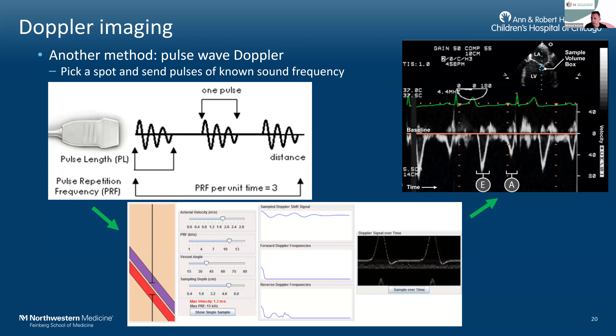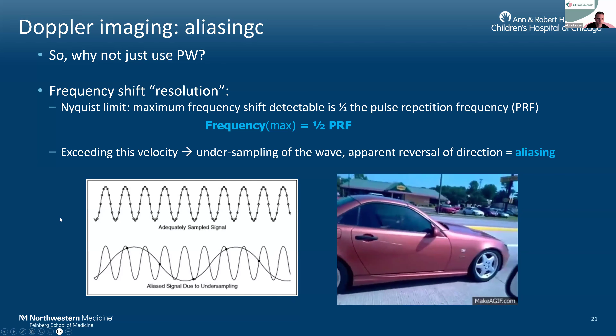The limitation of PW is that physics caps the maximum velocity that can be detected. In a famous equation by the physicist and engineer Harry Nyquist, the maximum frequency shift detectable, or Nyquist limit, is found to be half the pulse repetition frequency. Any velocity that shifts the frequency more than this will result in an apparent reversal of direction, a phenomenon called aliasing, kind of like what happens with a camera that films a rotating tire that starts to rotate faster and makes it look like it's going backwards. So using all of the equations that we have seen today, we can calculate the maximum velocity that can be detected in any given situation.